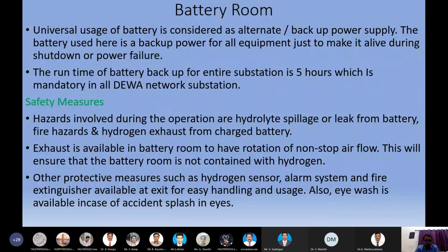The hazards involved during operations are electrolyte spillages or leakage from the batteries, fire hazards, and hydrogen exhaust from the battery charger. Exhaust is available in the battery room to maintain non-stop airflow rotation, so that during charging, the hydrogen exposed is exhausted from the room rather than contained inside. Additionally, there are hydrogen sensors, alarm systems, and fire extinguishers available at the exit of each handling and usage area. There is also an eye wash station in case of accidental spillage of the electrolyte into the eyes, so we can splash it instantly to avoid injuries.